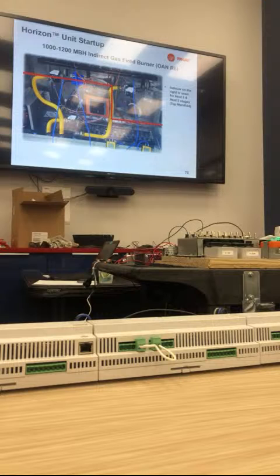And just for full disclosure, we've also got a quality problem with our insulation, but also the wires themselves. Those control boxes come to us loose. We're mounting them. Well, we did not secure those wires properly to the manifolds. They are laying right across those tubes.